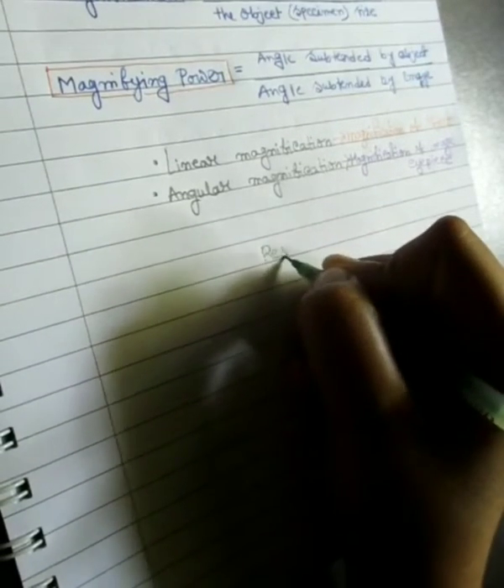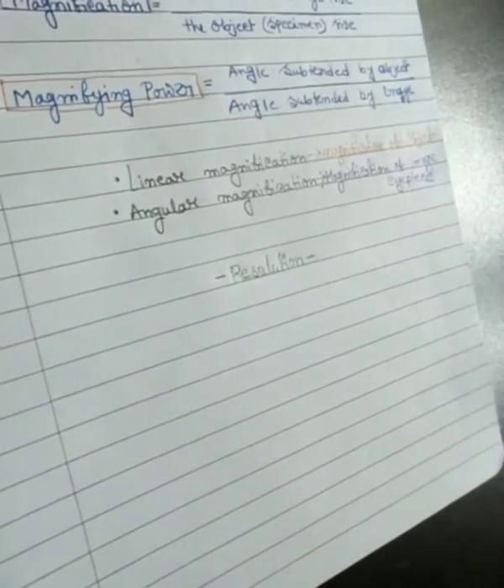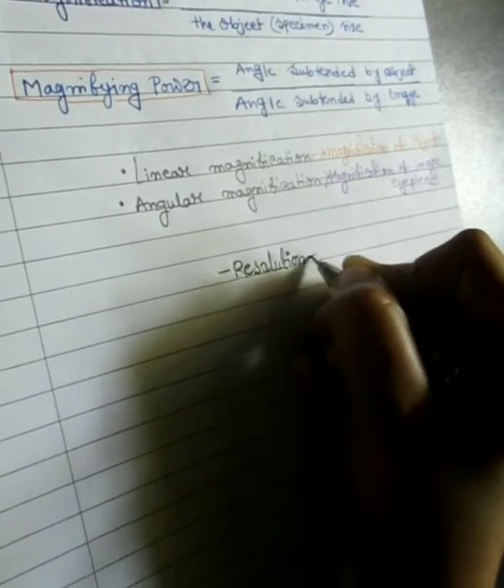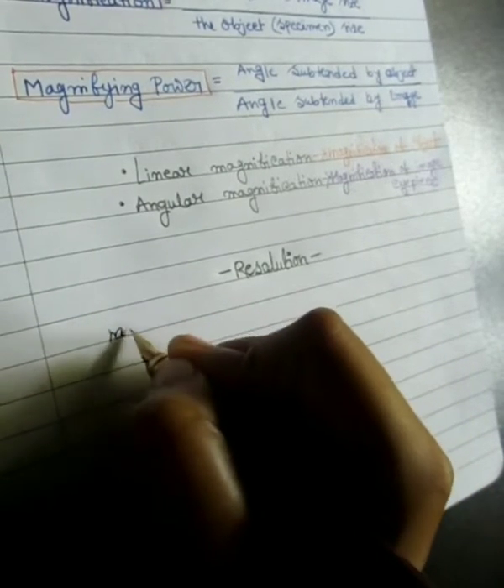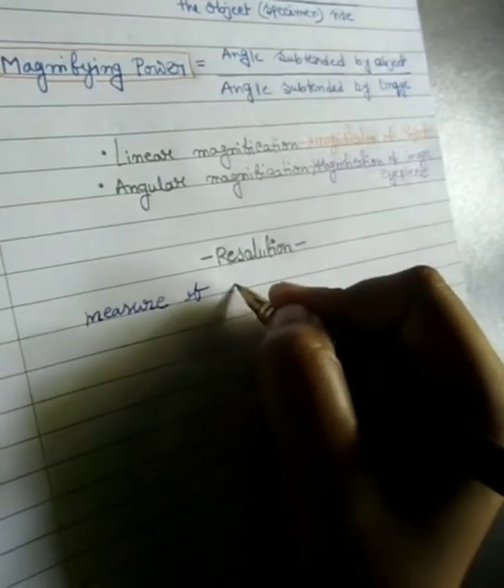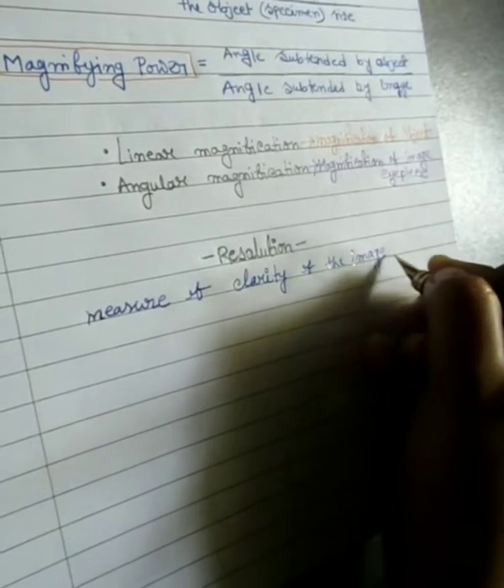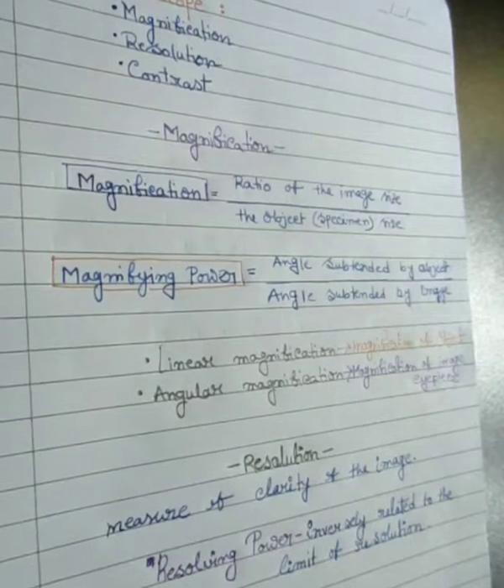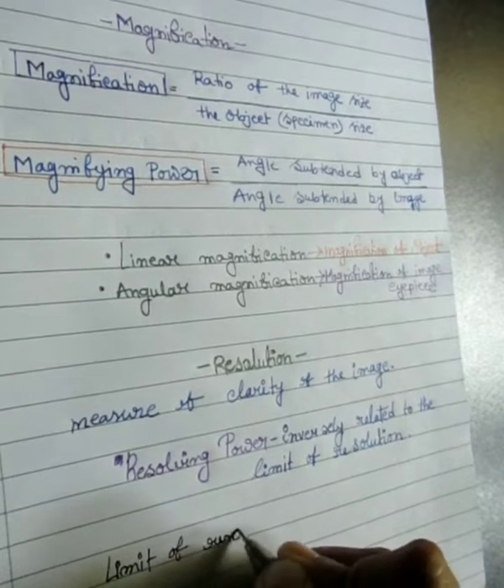Resolution is a measure of the clarity of the image. Resolving power is the ability of a magnifying instrument to distinguish two objects that are close together. The resolving power is inversely related to the limit of resolution. The limit of resolution is defined as the minimum distance between two points that allows for their discrimination as two separate points. Thus, the higher the resolving power, the smaller the limit of resolution.